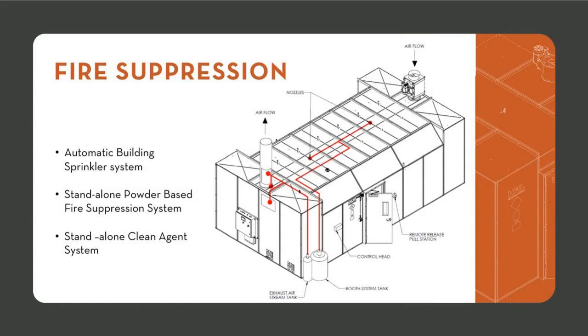And then the last option, which is less common, I believe only due to the fact that it's much more expensive, is a clean agent system. A clean agent system can be utilized the same way as a dry powder system. It's a standalone option, not tied into the building, but it uses a different suppressant that doesn't damage your extraction equipment or your biomass nearly as much. We've actually had a customer that has had the powder-based system go off, but really didn't have too much of an issue recovering their equipment and getting their equipment back into good shape. So there are many options for fire suppression, but it is compulsory to have fire suppression within these rooms.